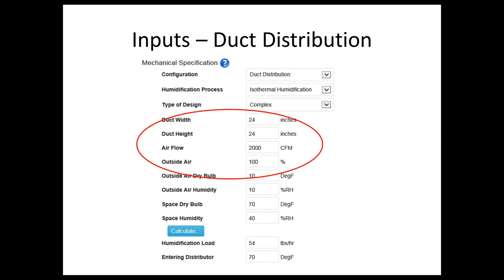Duct height and width are critical — this is something you really shouldn't be guessing at. First, because we size the distribution tube that goes in there. Second, that determines the velocity of the air passing over the distribution tube, which determines the absorption distance. You should get the exact dimensions of the duct.